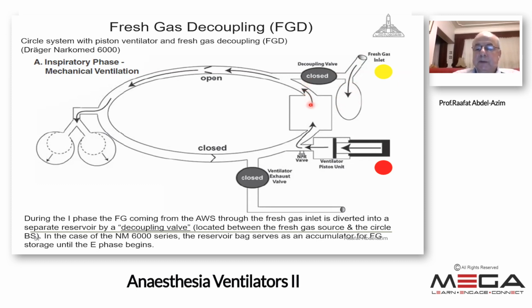What will be given to the patient is the content of the piston. During inspiration, it will go into the inspiratory limb, inflating the patient's lung. So during ventilation with the fresh gas decoupling system, you will see both are inflating during inspiration: the patient's lung, because of what is coming from the ventilator, and the reservoir bag, because of what is coming from the fresh gas flow. Of course, fresh gas flow will contain oxygen and inhalation anesthetic.